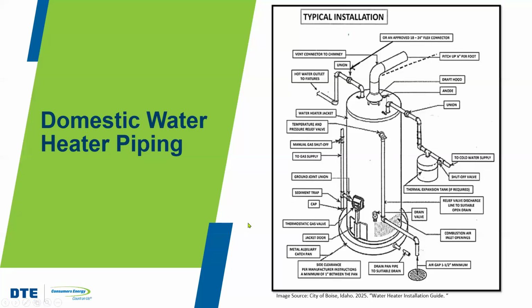We want to have some pressure and temperature relief valves. They can either be separate or they can be combined. If this water heater is used for space heating, then we want to make sure that it's got a master thermostatic mixing valve, right? An anti-scald valve, if you will, to make sure that the temperature of water that's sent to the domestic purposes within the home is less than 140 degrees.